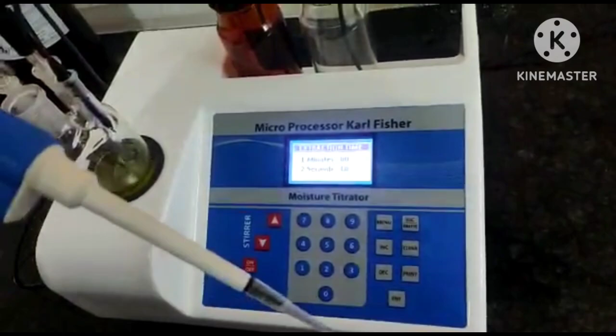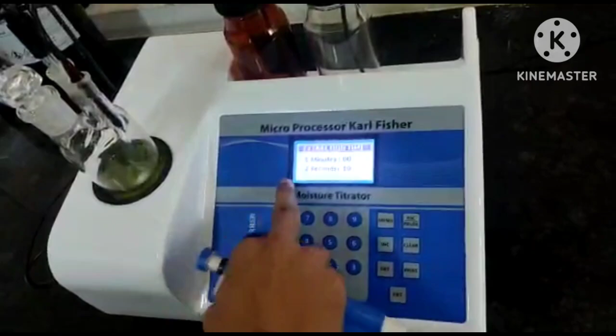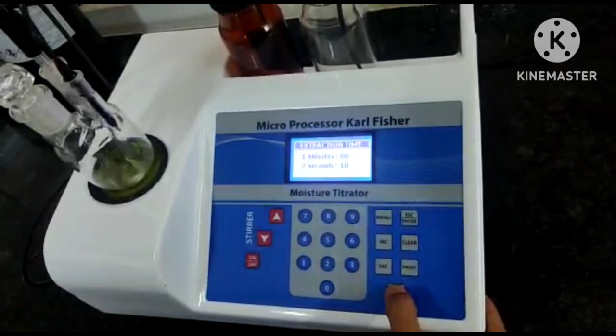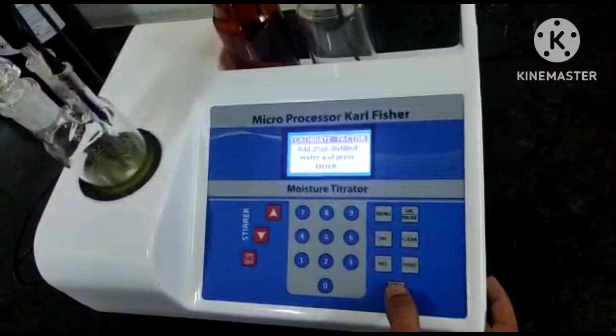So now we have to pour 25 microliter. I have taken 25 microliter. We have to pour it inside, and we have selected 10 seconds, which is okay for distilled water, as it can get extracted within 10 seconds. So there we have to press enter. After that you will get a message, we have poured in the distilled water, then we have to press enter.